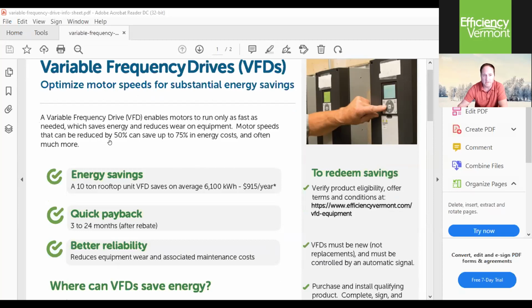Motor speeds that can be reduced by 50% can save up to 75%. This gets at that sort of cubic relationship. When you slow a motor fan down 10%, you don't get 10% of energy savings, you get 25%, which is why this technology is so cool. We've got a small example here on a 10 horse rooftop supply fan. A drive on that saves about 6,000 kilowatt hours a year, $915.